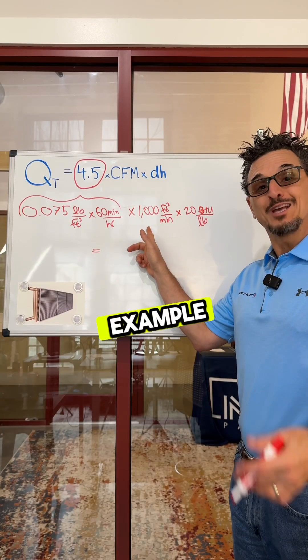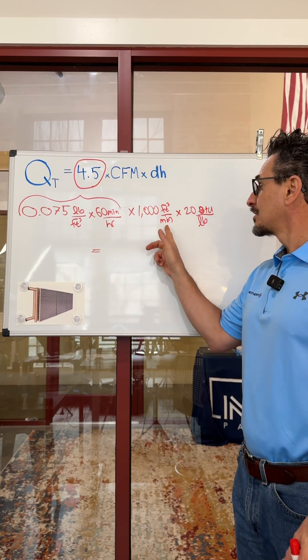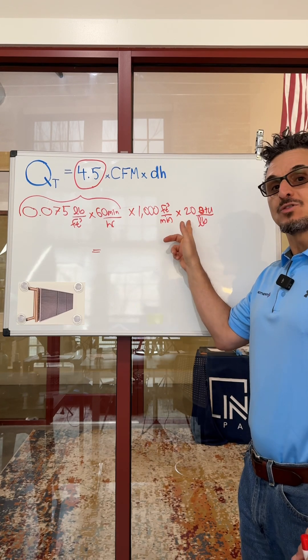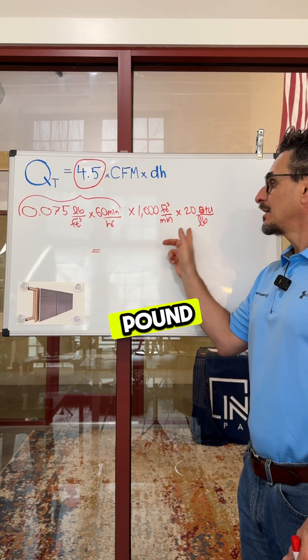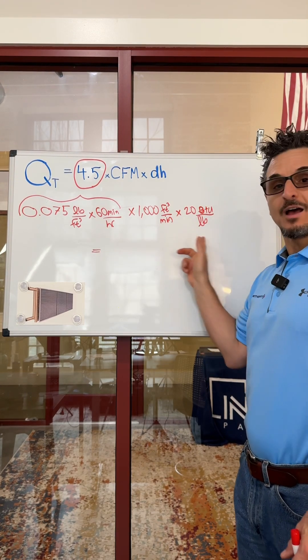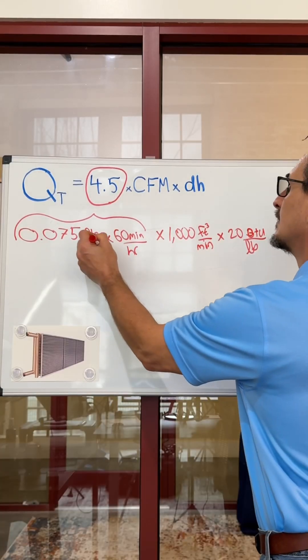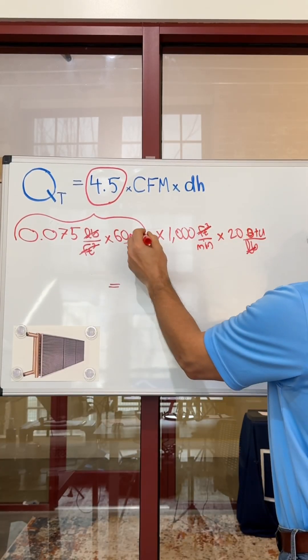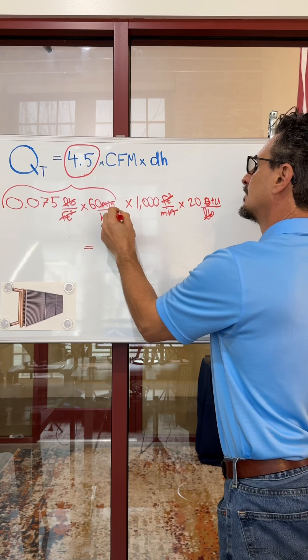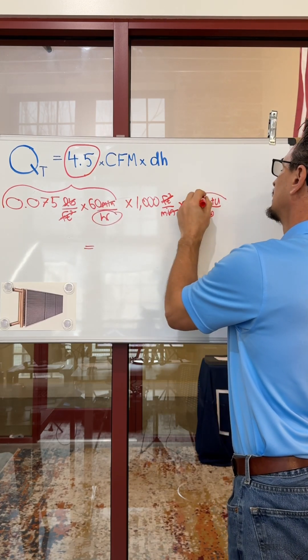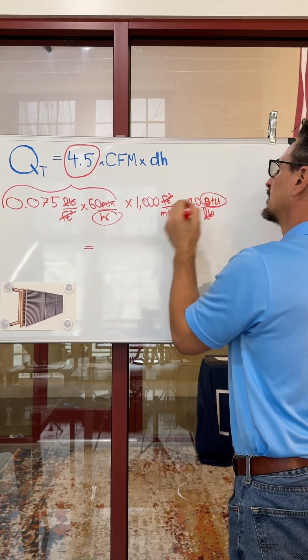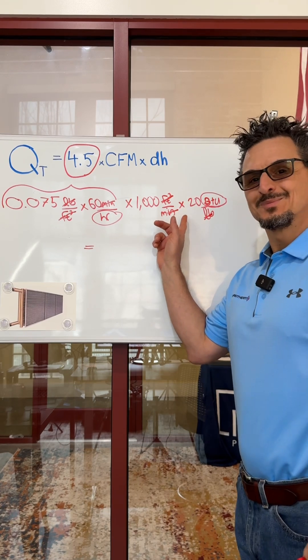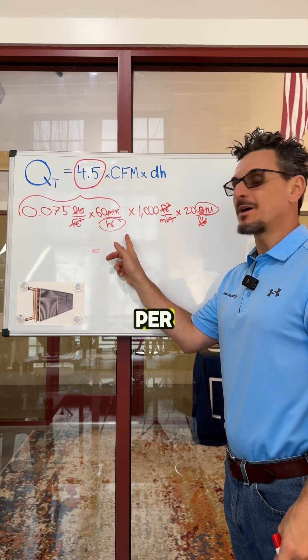For example, let's say 1,000 cubic feet per minute, with a delta H of 20 BTUs per pound, and let's see how this works out. You can see you're left with BTUs per hour.